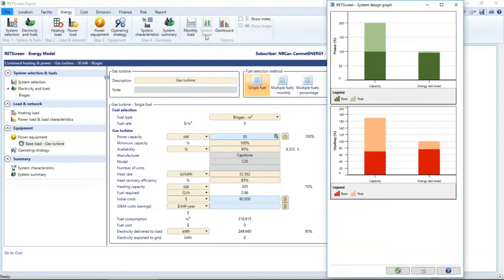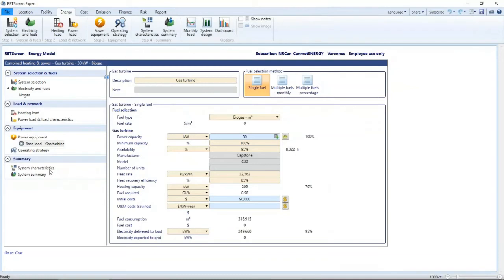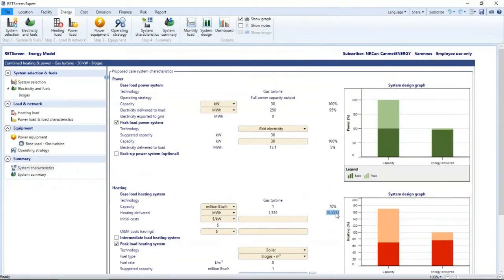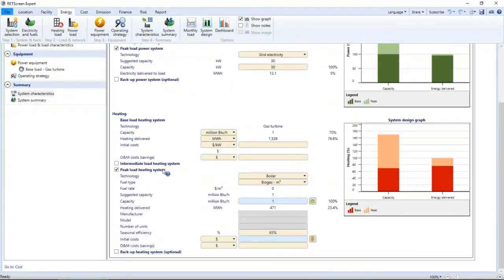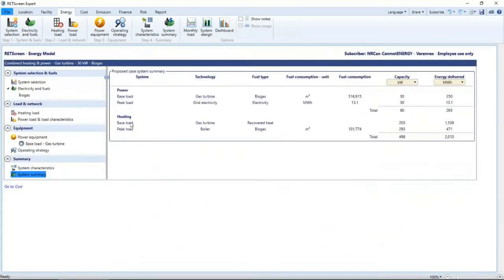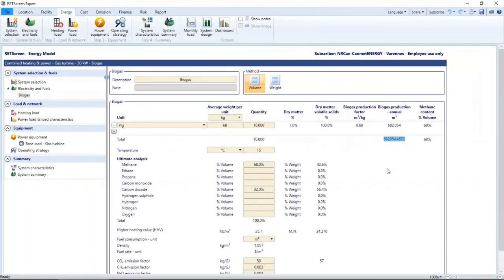The gas turbine will operate at a full capacity, providing 30 kilowatt of capacity all year, except for 5% of the year when the system is not available. All the electricity will be consumed on site. The heat recovered from the turbine will provide more than 76% of the process heating load. I could verify in the system characteristics section that the remaining heat required will be provided by an existing biogas boiler. In the system summary, I could calculate the amount of biogas required on an annual basis, a little over 400,000 cubic meters, and verify if the farm could provide the required amount. Yes, the production is large enough.